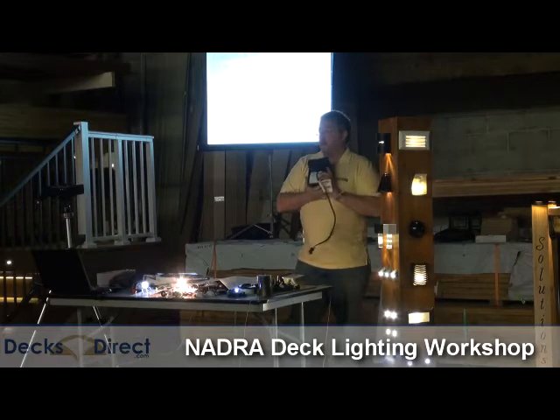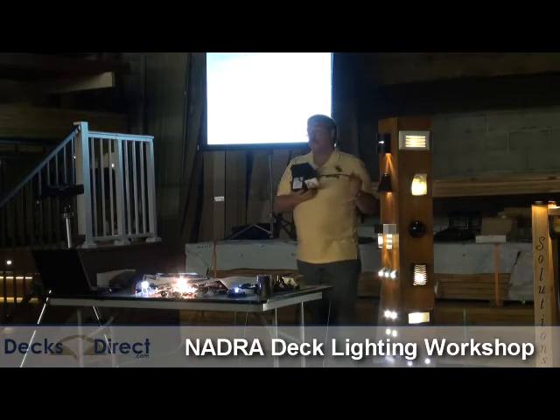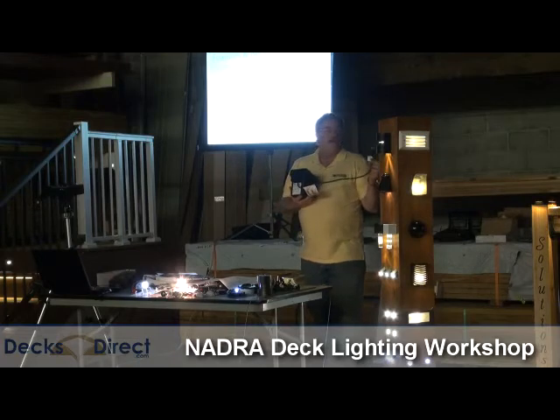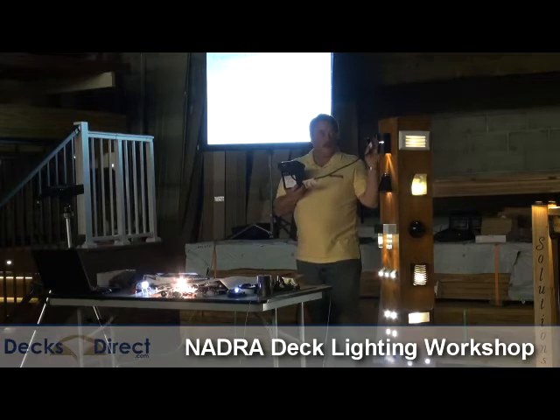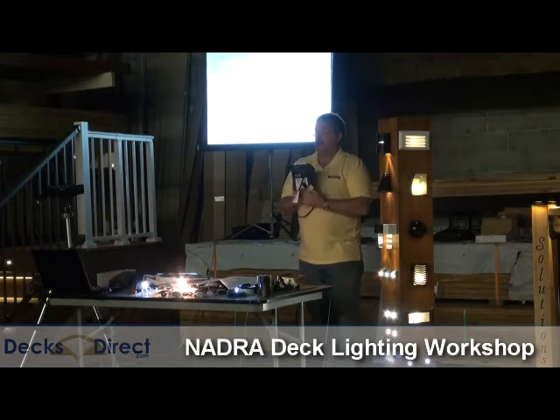Read the UL listings on the transformer. One of the things the building codes say is that we can install devices as long as they're UL listed. The city of Plymouth said this particular style of transformer had to be hardwired into the circuit, but the UL listing doesn't allow it to be. We actually battled the city, and after some time we won that battle.